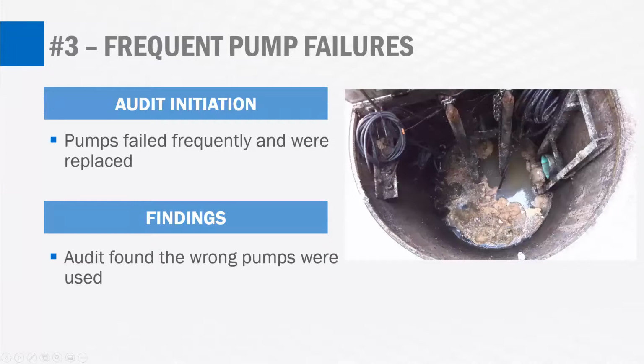Case study number 3 involves pump stations that have frequent or recurring failures. In this case, the failure was associated with the pumps themselves. This station was a smaller station, but the pumps kept having to be replaced every 2 to 5 years. At first, there wasn't a lot of thought given to why these pumps were failing, why they had to be replaced.